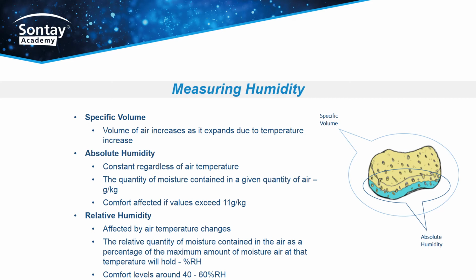There is a huge focus on temperature when trying to achieve comfortable conditions within a building. However, the importance of the correct humidity conditions should not be overlooked, as this also has a significant impact on occupant comfort. Generally, conditions between 40 to 60% RH will be comfortable for most people, though the absolute humidity does play a role in thermal comfort too, when it gets to very high levels. Absolute humidity is the mass of water in grams per mass of air in kilograms, and is constant regardless of air temperature. Having more impact on our comfort, relative humidity is dependent upon the specific volume of the air. Like any other substance, air expands and contracts as it changes temperature, and therefore the specific volume of a kilogram of air will change as the temperature changes.